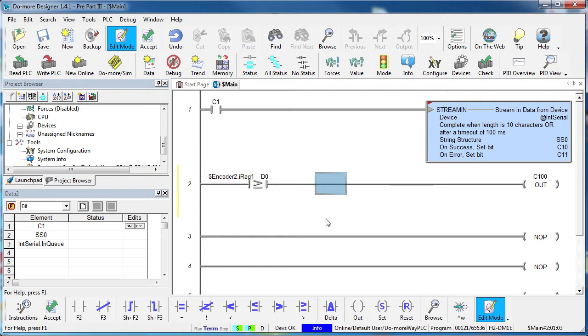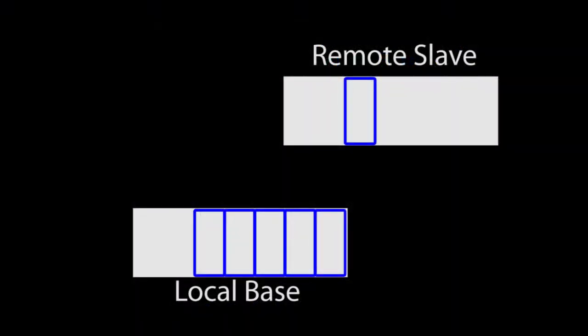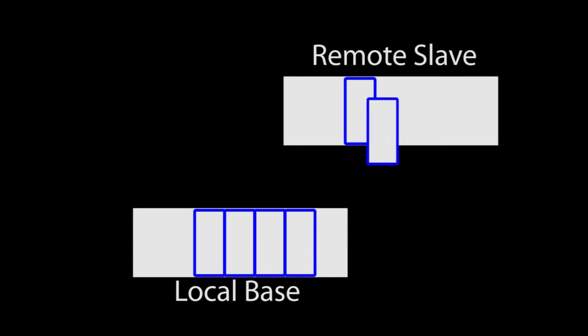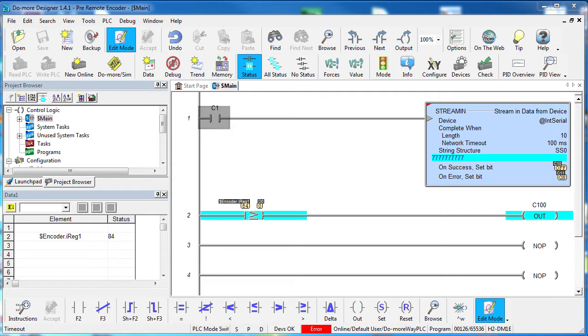And there's one more side effect of using this device centric model. What would happen on most PLCs if you actually removed the module from the local base and put it in a remote base? Yeah, it would break all your code and you would have an enormous amount of work to do to get it back up and running, right? Let's see what happens when you do that on the Do More. Let's power down the Do More and move this counter I-O module from this local base to a remote base on the same network. Power up the system. The Do More immediately sees that that counter I-O module is missing and gives us an error.